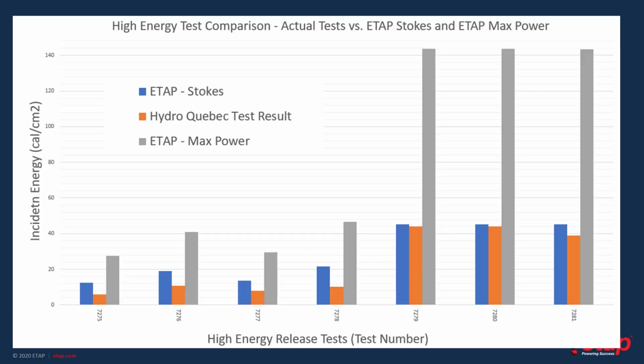Okay, so after we've seen this test, now we can look at the results. Of course, we don't have time to go through every test, but we can look at how we fared through the majority of tests. We're looking at simulation results for tests 7275 and 7279. 7275 is right here, the first test, and 7279 is the big, lots of current, lots of time test. Focusing only on test 7279, we can see that the ETAP result is within a fraction of a calorie difference. Of course, this is done with one adjustment that we must take into consideration.